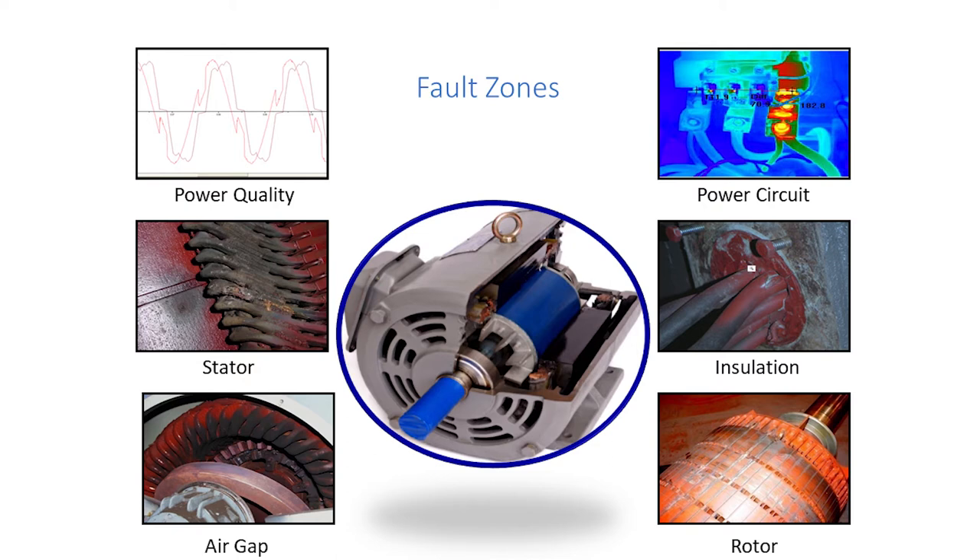What's interesting is the insulation between the stator turns and the insulation to ground is the same material — but looked at very differently. Remember that DC motor that was good on the ground test? It would have passed the insulation fault zone, but it failed miserably on the turns fault zone. Different measuring techniques are required. It's important to segregate those two: a megohmmeter test is not the end of the day — it's a great test, but not the total picture.